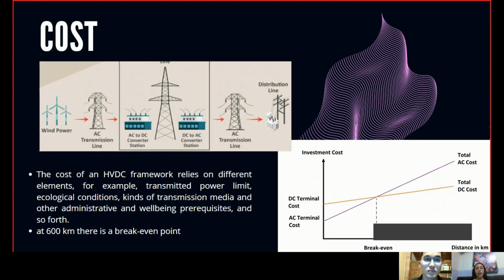The installation cost of the HVDC system is higher than that of the HVAC transmission system, since naturally the voltage or current can only be increased or reduced by means of power transformers. In addition, in HVDC transmission, we have HVAC power transformers at the end of the line. Then there is the converter station that converts the intensified AC power into DC power. This power is transmitted over transmission lines, and at the end there is an inverter station that converts the DC power to AC power. What really increases the cost of HVDC installation are the converter and inverter stations compared to HVAC. To have a better understanding of this, let's look at the graph.